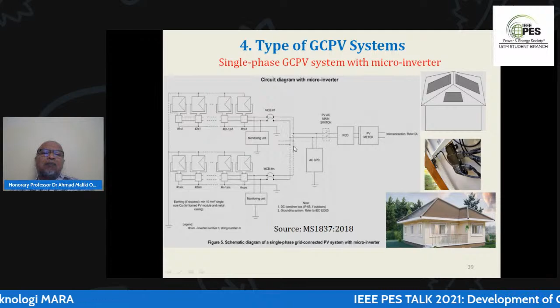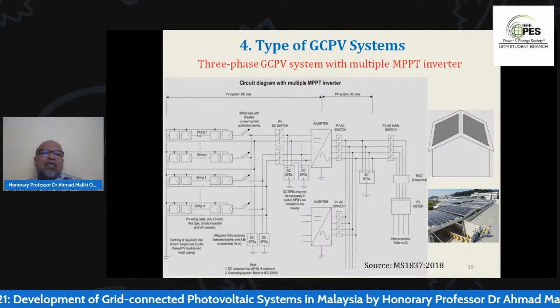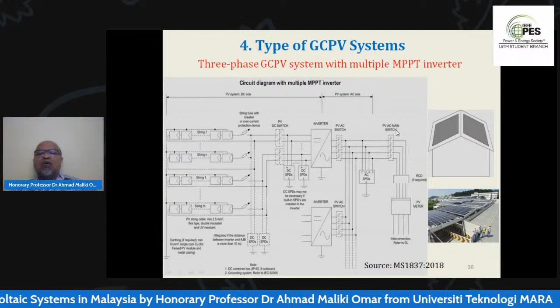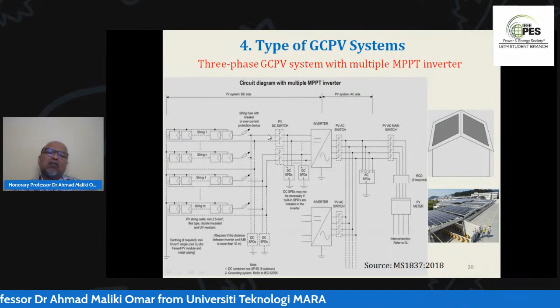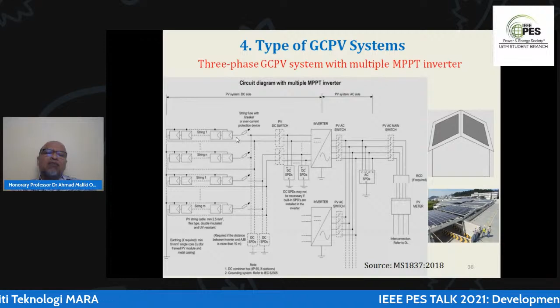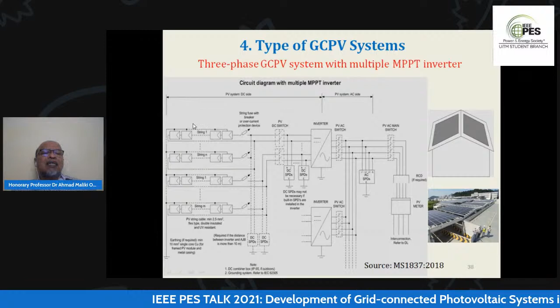For the system I mentioned before, the multiple MPPT inverter, if the building caught fire, you turn off the AC switch, you turn off everything, but the voltage here will still be very, very high. It's quite dangerous, you cannot touch it live. The voltage can easily go up to 800 or 900, depending on how many modules you design in the string.